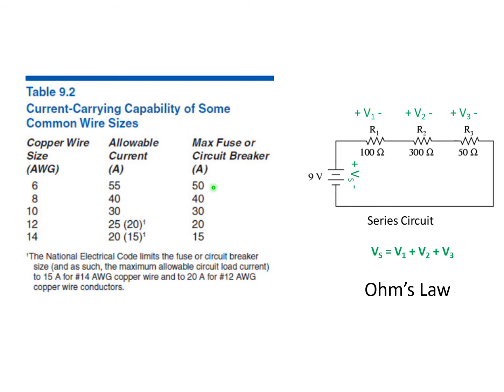Now, where this may come in at a later time is if you want to buy an amplifier, an HF amplifier, say a 1500 watt amplifier, unless you happen to have a service already in the house, you'll probably have to add another run of either a 40 amp or a 50 amp breaker if you want to operate the amplifier safely. And the supply current and voltage will be specified by the amplifier maker. So you'll just want to make sure that you're getting the installation of the proper size wire and breaker for the load that you're going to have on the amplifier.